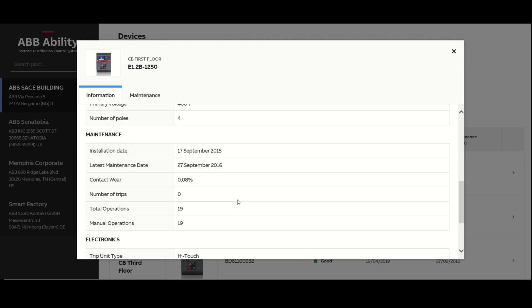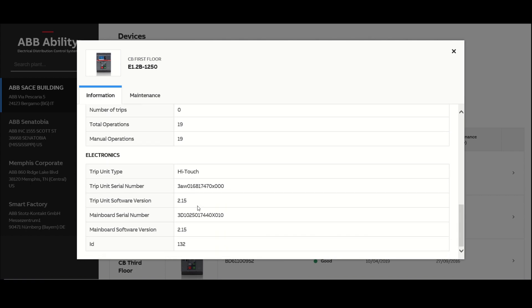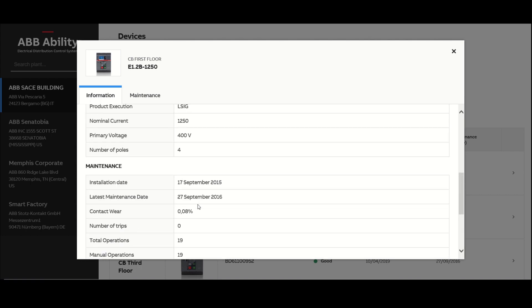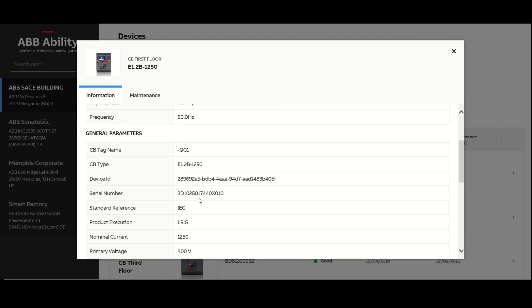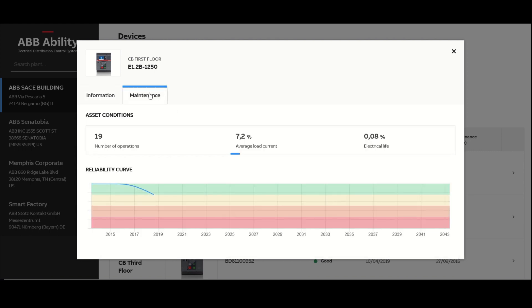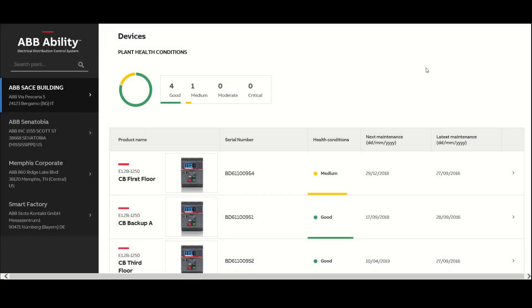ABB Ability EDCS uses an algorithm to keep track of a device's usage. It can inform you of the health of the device, where it is in its useful life, and when maintenance is recommended. The predictive analysis takes into account key factors such as the number of mechanical operations, nominal current, overloads and short circuits, and environmental conditions such as humidity, temperature, vibration, and corrosion.